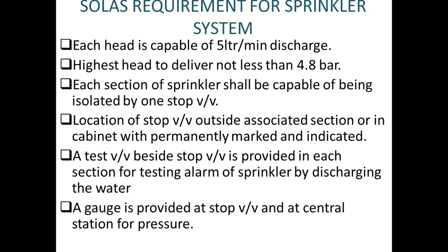A test valve is also there for testing, because as per the SOLAS requirement we have to do this testing in routine. So a test valve, besides the stop valve, is provided in each section for testing the alarm of the sprinkler by discharging the water.